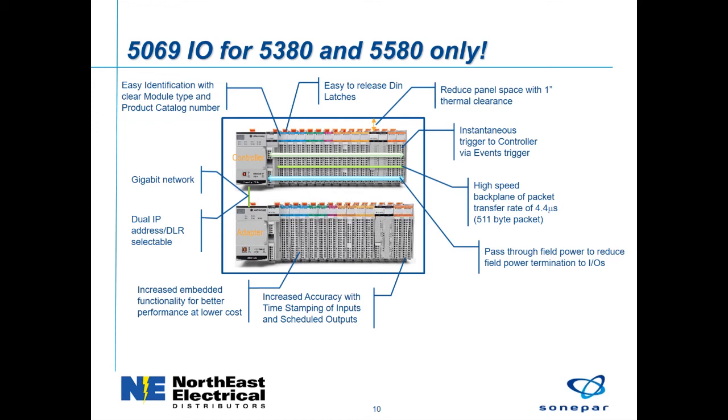Wiring is much better. It's a removable terminal block on the front. The terminals actually line up with the indicators for your inputs and outputs. Makes it easier to diagnose and troubleshoot. And it's extremely fast. It's an order of magnitude faster than the previous products. For example, digital input to a 5380 controller and back out to a digital output takes about half a millisecond.